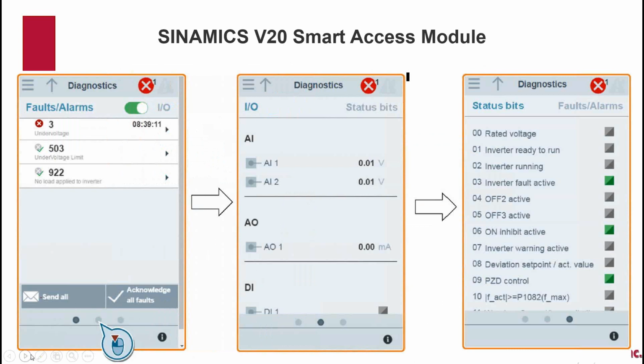At the bottom of that screen, you've got the 3 dots. Each of those represents a different page. If we click in the middle, it's going to pop up this diagnostics page. It's going to show us analog input, output, and digital input, output status. Very handy for troubleshooting to know, what's my speed pot actually set to voltage-wise, or what digital inputs are on. I think this one's on. Is it really on? Then the 3rd page shows us a status word back from the drive that shows you 16 bits basically of information about what's going on in the drive.